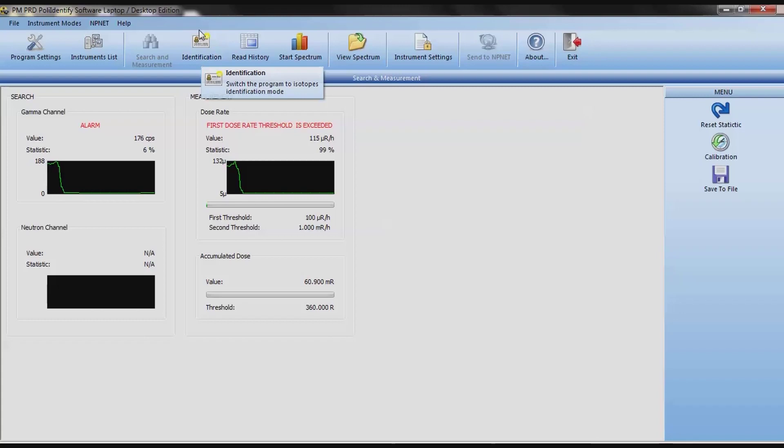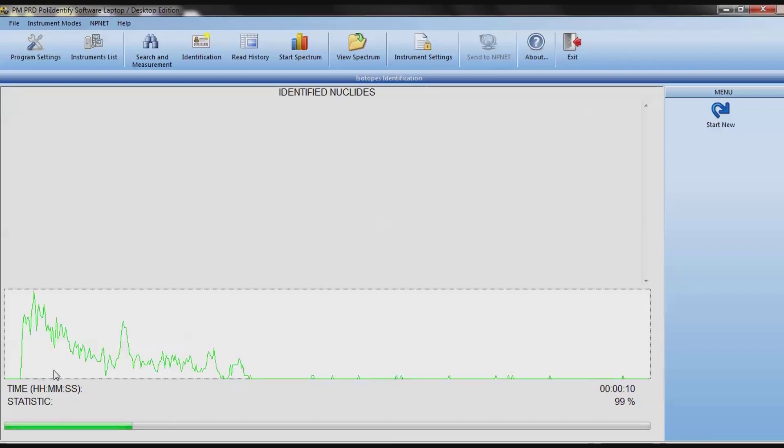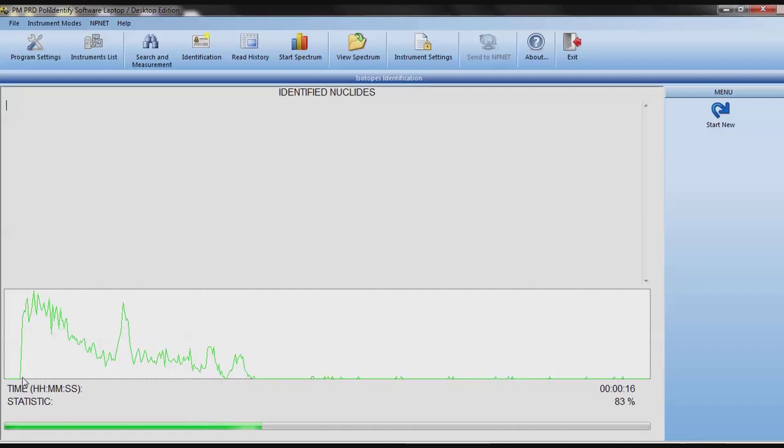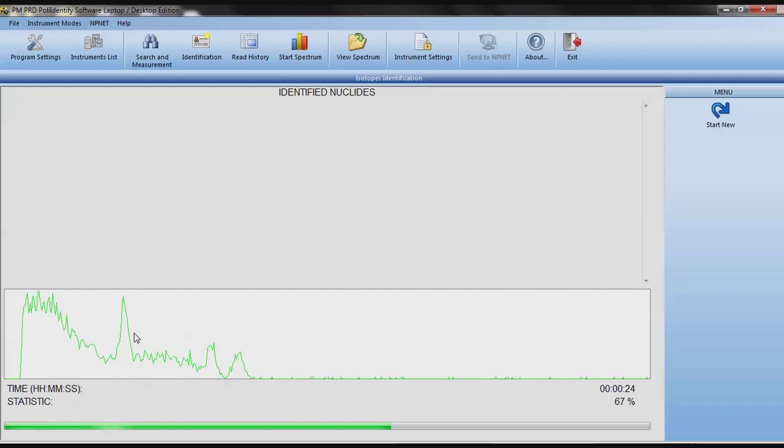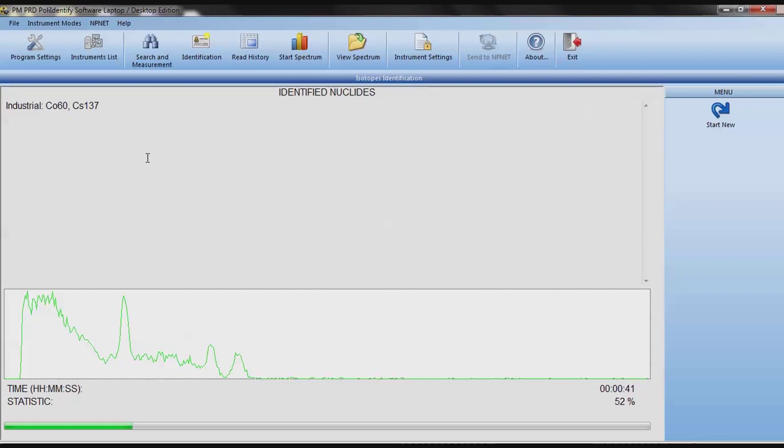Click this button right here, the auto isotope identifier button. And let's let the unit go. Now you're going to see a screen in front of you here. The bottom, the x-axis, is energy from low energy on the left, moving to higher energy as you go on the right. That's the energy of the gamma rays that hit the unit that it senses. And the up and down part, the y-axis, is the number of counts in that particular amount of energy. And you see there's a big spike, several of them in fact. That one right there, I know exactly what that's from, and then the other two over here in the end. Those are the actual peaks coming from the actual things that we have in the box. And there it is. Industrial sources, cesium-137 and cobalt-60.